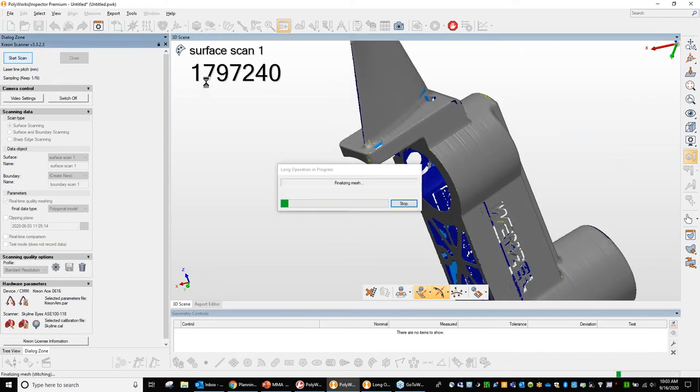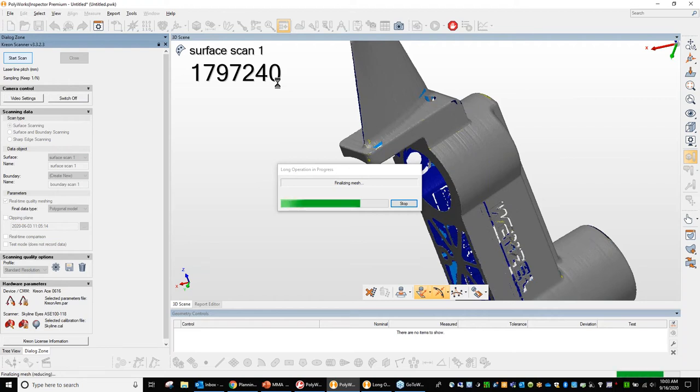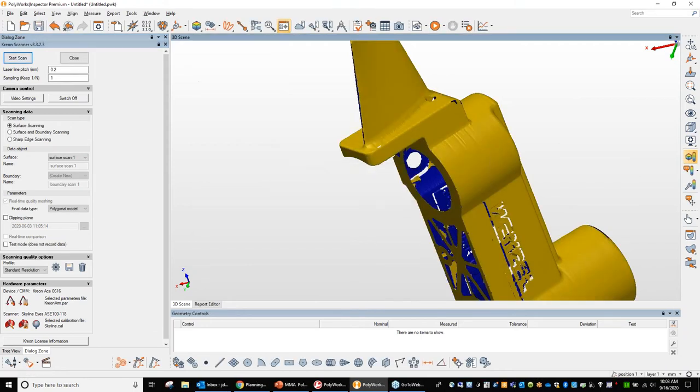Now it might take a little while because there's quite a few data points that came through. The laser scanner that I have on here is what we call our MLS 100P, which is a hundred millimeter line length blue line scanner. And I can collect up to 600,000 points a second. So once the scan completes, the blue areas indicate an internal feature and the yellow areas indicate an external feature.